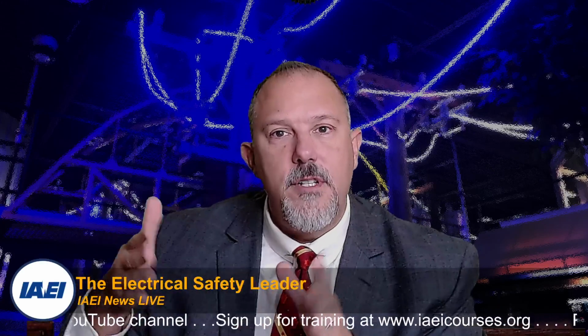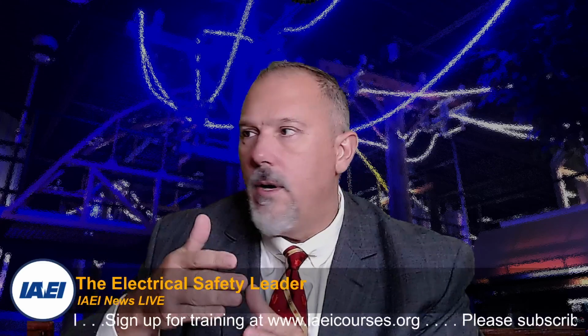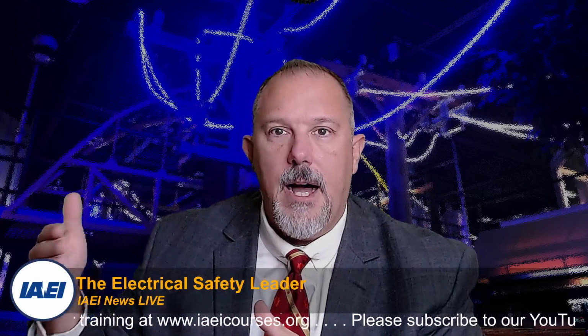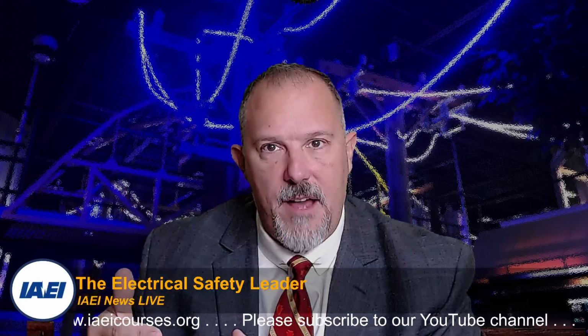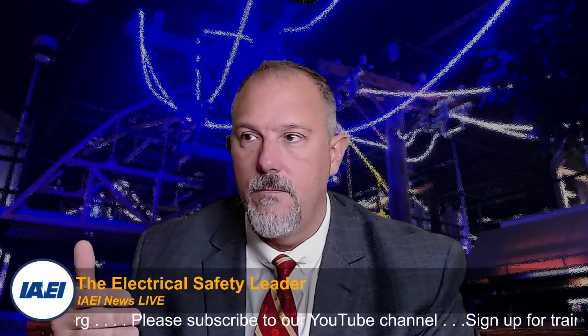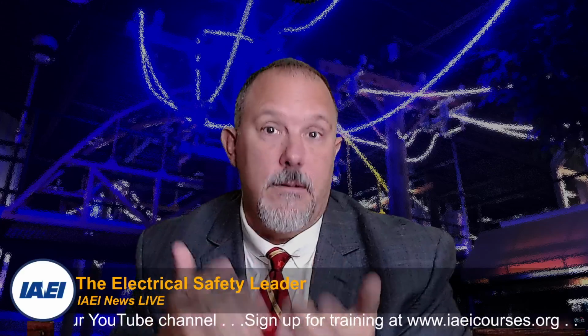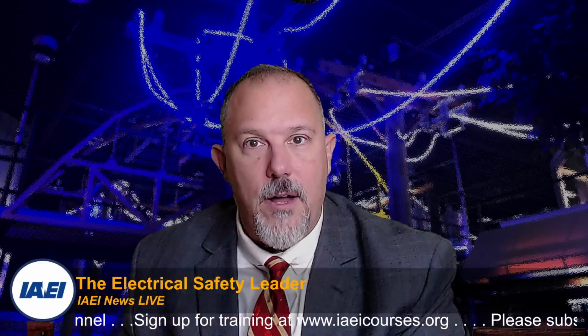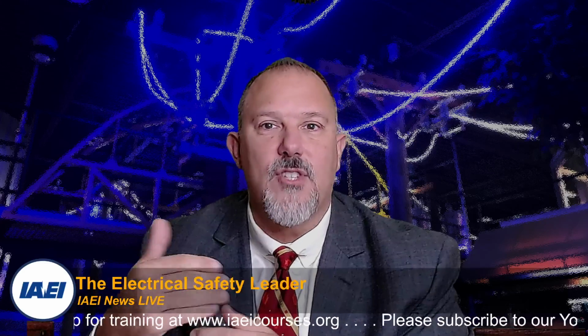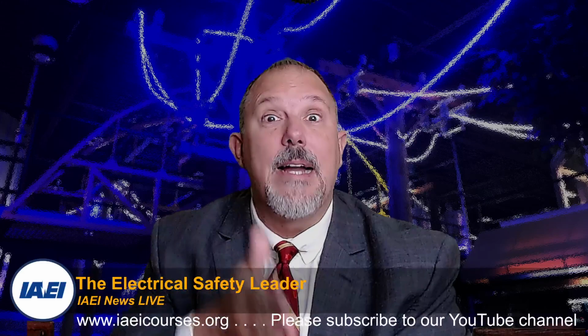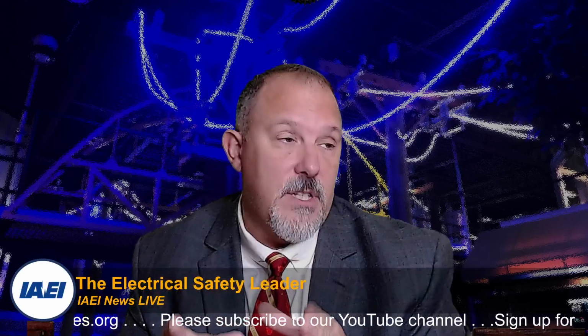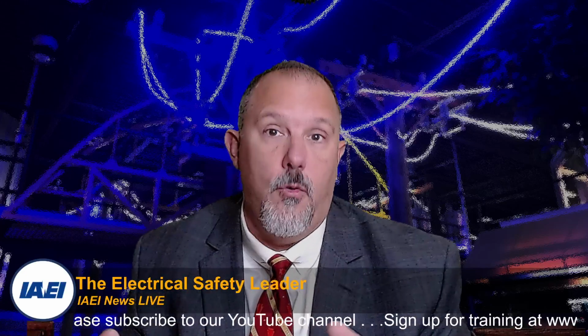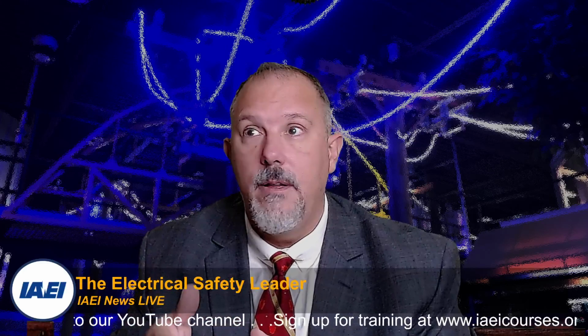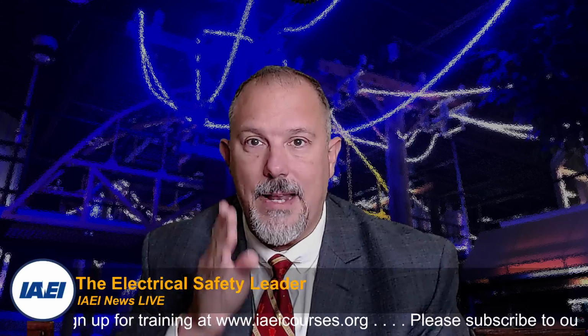Now, short circuit currents go outside the path. That means I have a load, I have conductors, and I've shortened my circuit. I have current somewhere in between, somewhere in that circuit. I have created an alternative path, directly to neutral or to ground, say a line to line fault, a line to neutral fault, or a line to ground fault, somewhere outside of the normal path. Think about a 120 volt single phase 20 amp circuit in your home. If I have a 100 foot run of conductor and I go at 50 foot and cause a direct short between line and neutral.